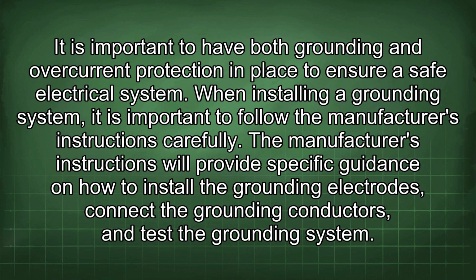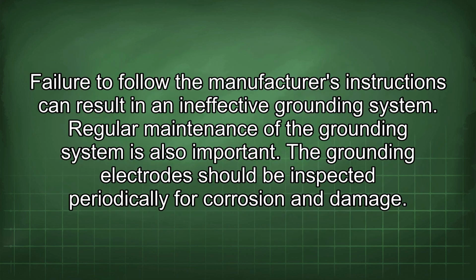When installing a grounding system, it is important to follow the manufacturer's instructions carefully. The manufacturer's instructions will provide specific guidance on how to install the grounding electrodes, connect the grounding conductors, and test the grounding system. Failure to follow the manufacturer's instructions can result in an ineffective grounding system.